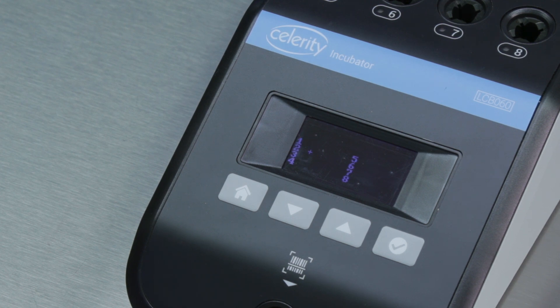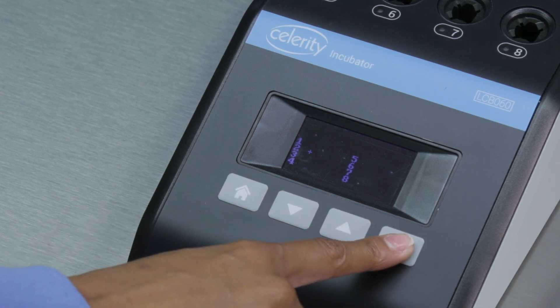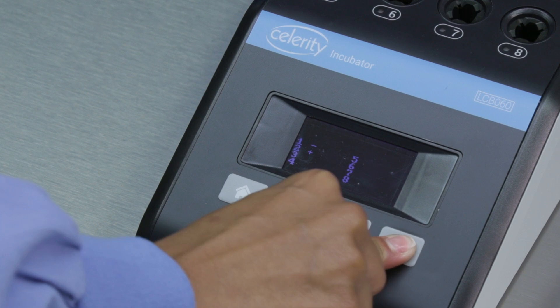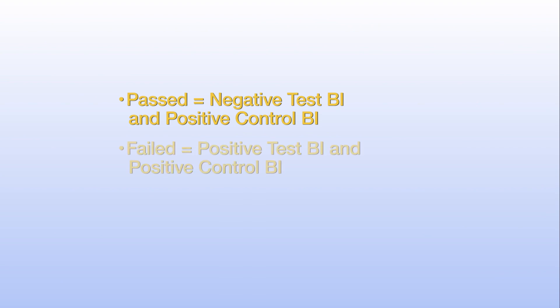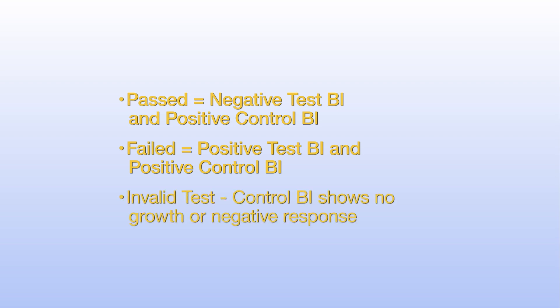The testing passes if the process BI is negative for growth and the control BI is positive for growth. The testing fails if the process BI is positive for growth. If the control BI demonstrates a negative response or no growth, the results are invalid and testing must be repeated.